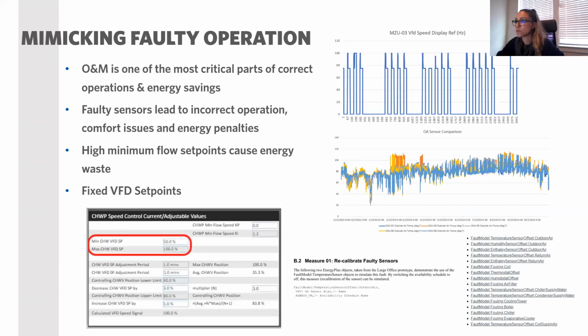And the next one is more on the RCx side, looking into faulty operation. Especially if you have BAS data, this is what we typically spend our time on. I want to highlight O&M. O&M is probably the most critical factor after the measures are designed and constructed, and it becomes the most important piece to make sure that these controls are actually running correctly. Because if a sensor goes out of calibration, you can see in that example. In this example, there are 5 outside air handling units, and they all have their individual outside air sensors, which is great.